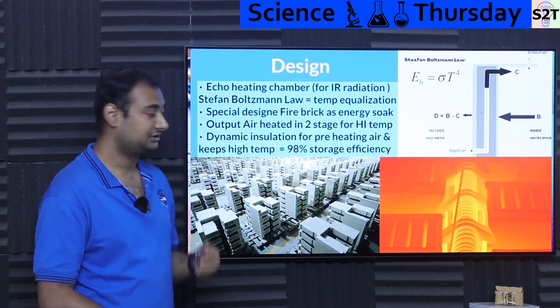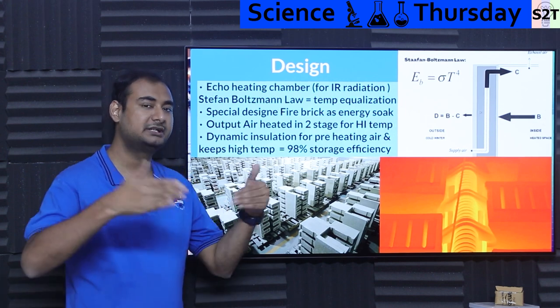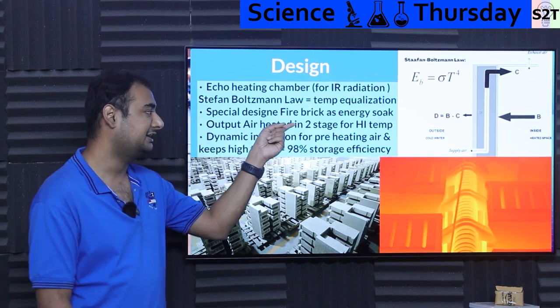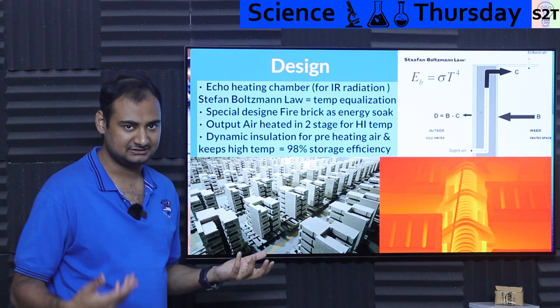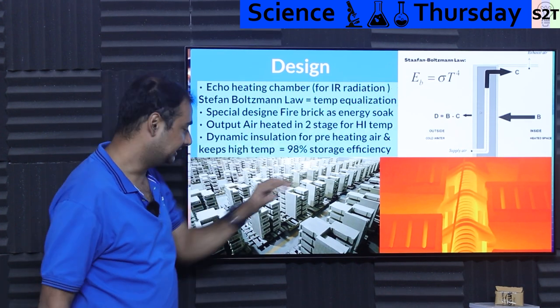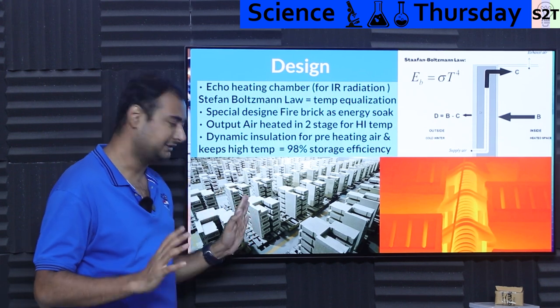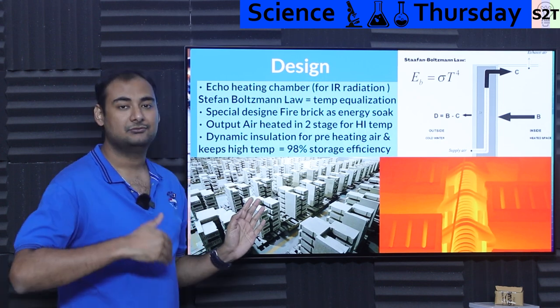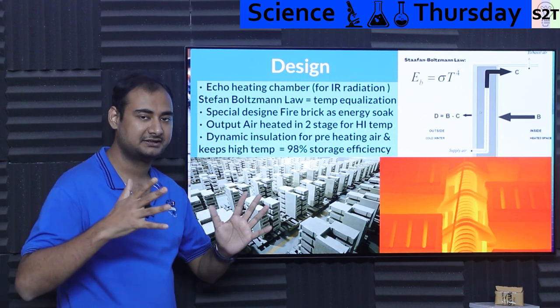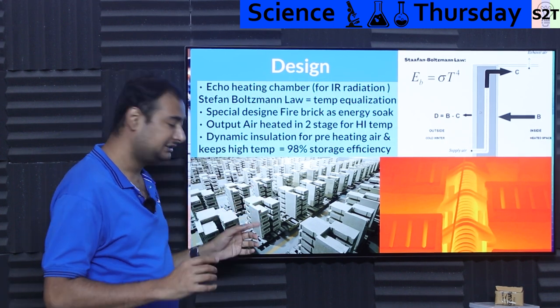That's a very big advantage of this design. Everything inside the chamber will slowly and uniformly rise and fall in temperature rather than having hot spots. Compared to other systems where you dump hot air into sand which slowly conducts away — here it's bam, direct radiant energy transfer. The heat is stored in specially designed fire bricks — refractory bricks. This is not new technology, but the design is unique because it's fine-tuned for infrared reflection. They are not relying primarily on convection or conduction; photons are the primary energy carriers.